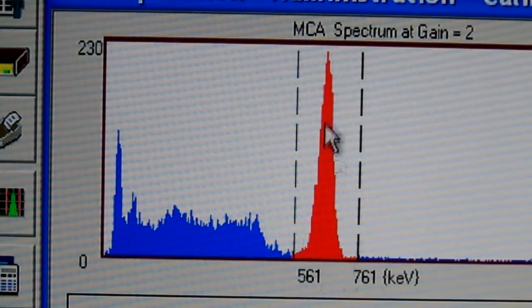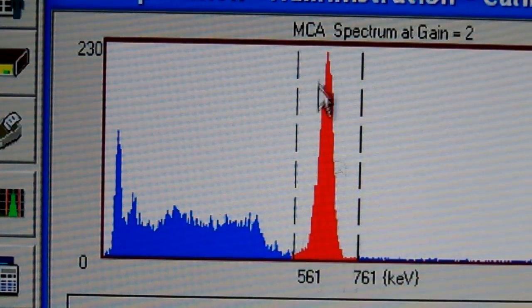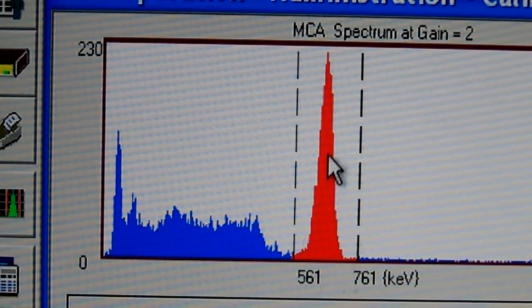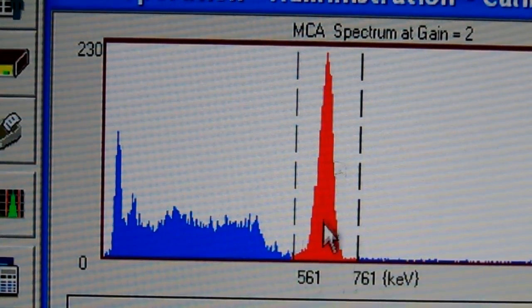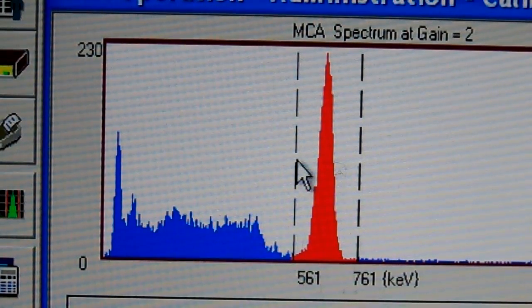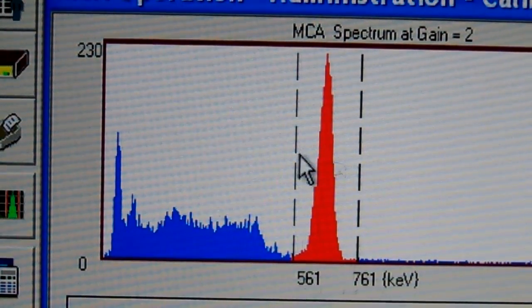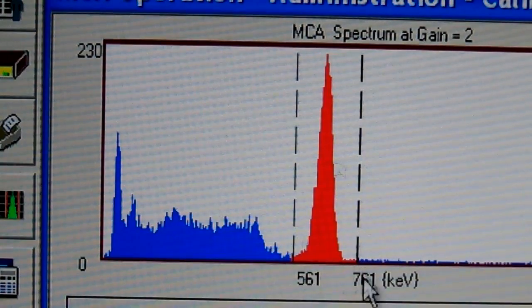Now you want to talk about your full width half max of your cesium peak. The full width half max is it goes halfway up the peak of your cesium source and takes that number divided by the difference between the two bottom numbers.